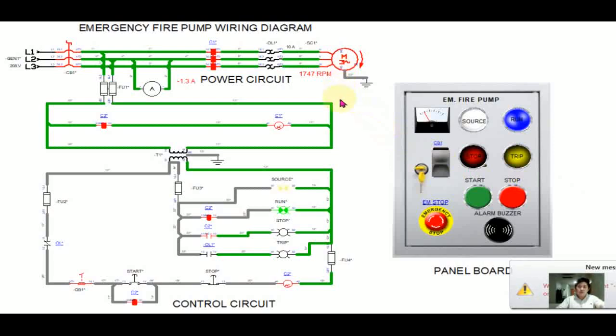So I will put additional load on the motor. What causes additional load on the motor? It's a fluid that is being pumped with the pump, and either the bearing is not in good condition anymore and is a little bit hard to turn, or the impeller is touching the inside housing of the pump. Or it's either the viscosity of the fluid being pumped, or whatever reason that the motor becomes overloaded.